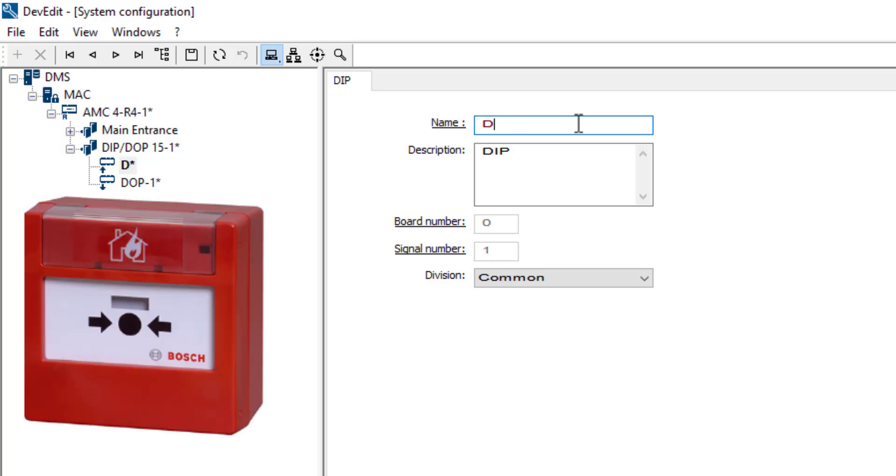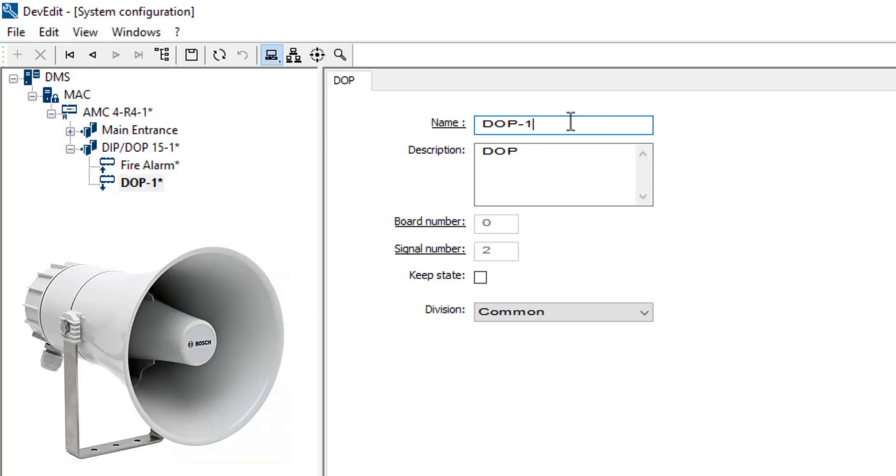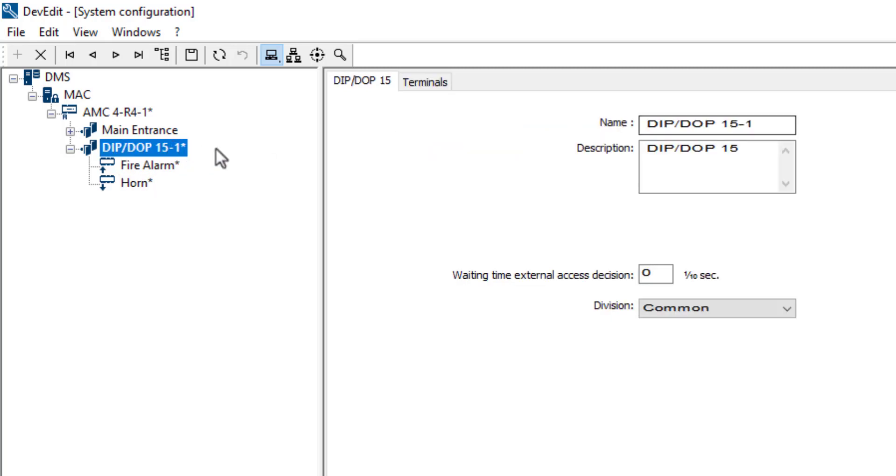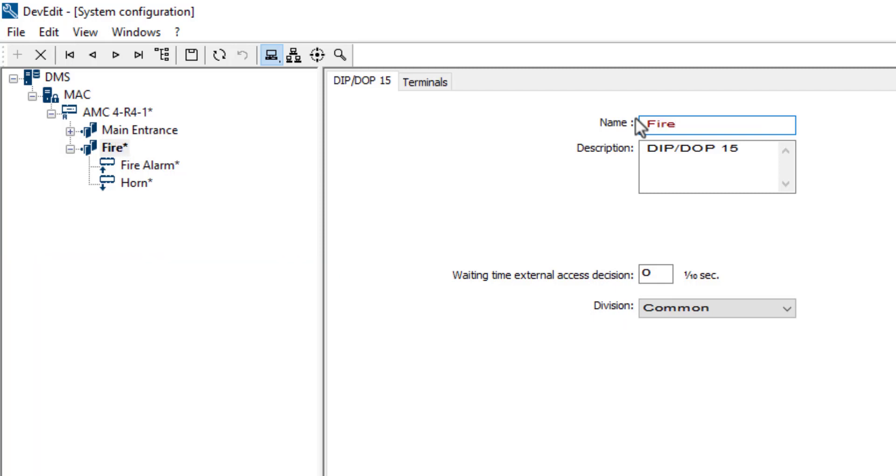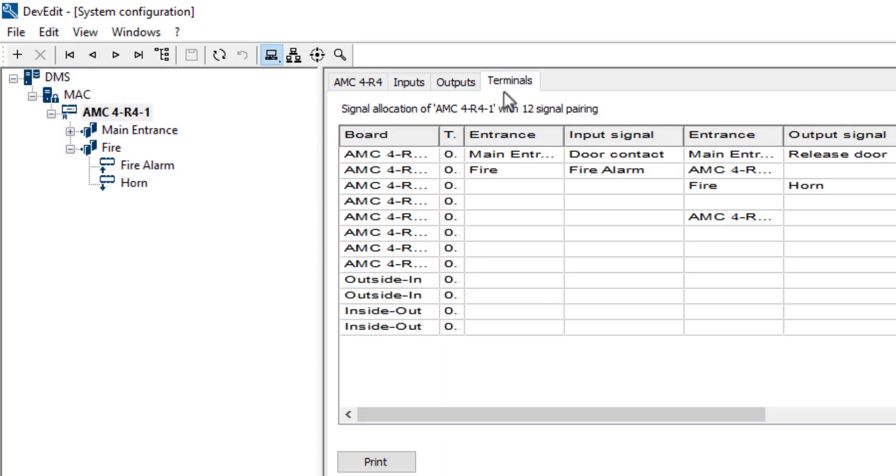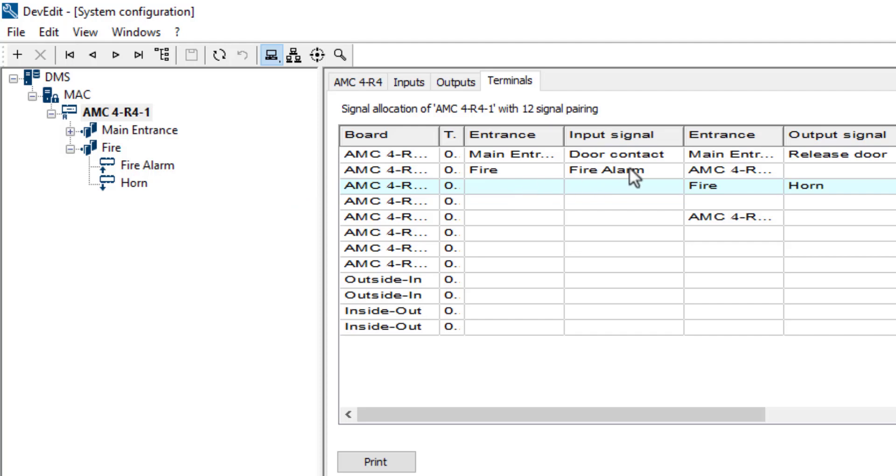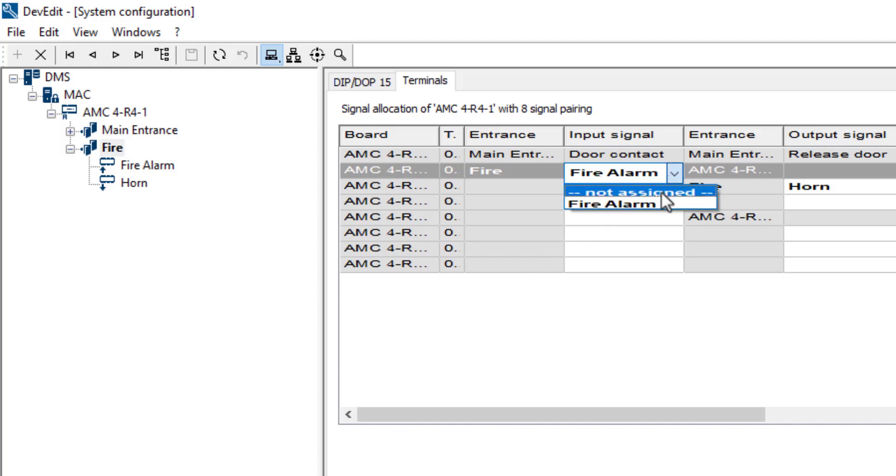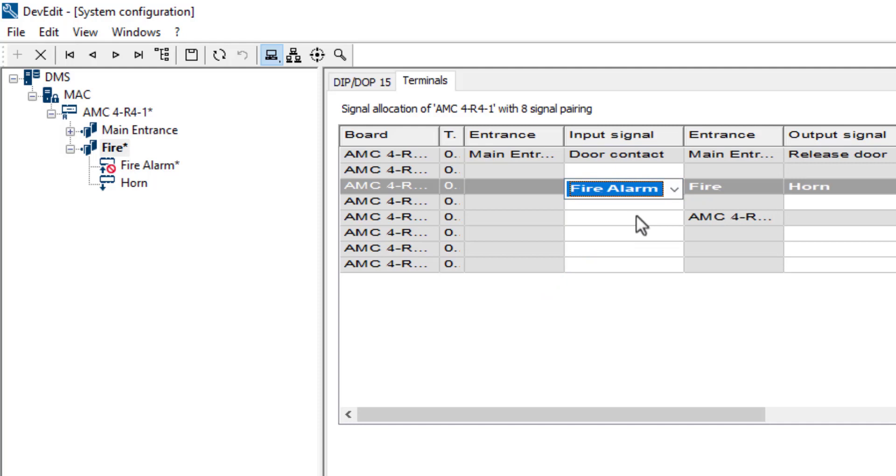The DIP is the fire alarming device. The entrance is simply called fire. Let's see where they are positioned in the terminal logic of the AMC. We notice that the input has gone to position 2 and the output to position 3. Those were the first free positions. Let's put the DIP on the same level as the DOP. We unassign the fire alarm from position 2 and assign it to position 3, on the same level as the horn.